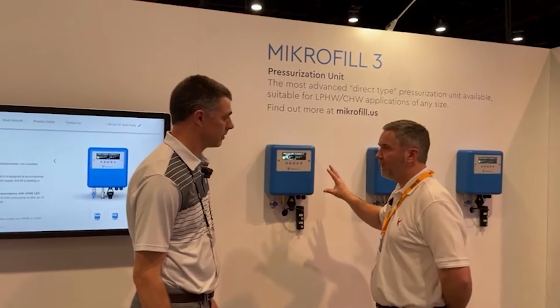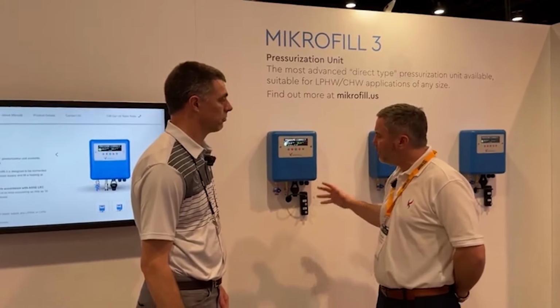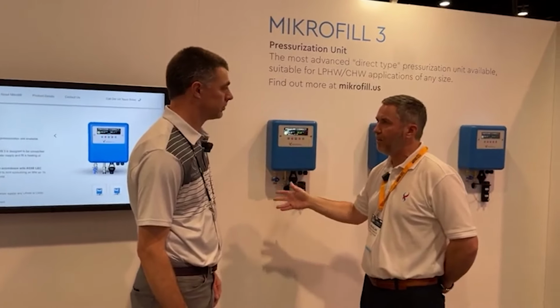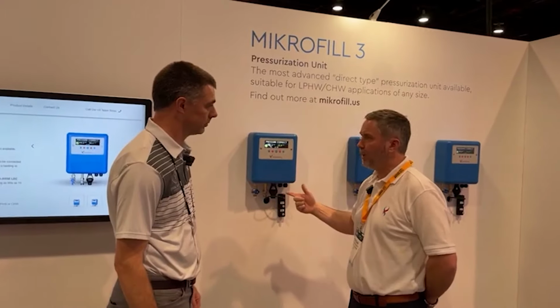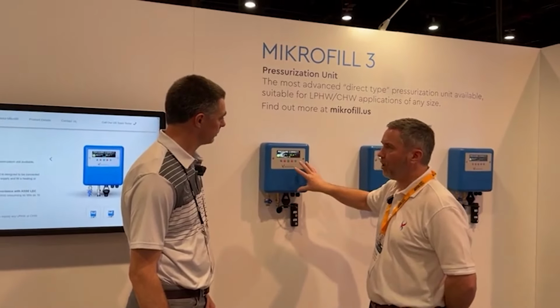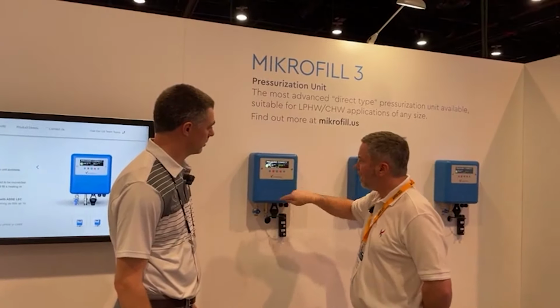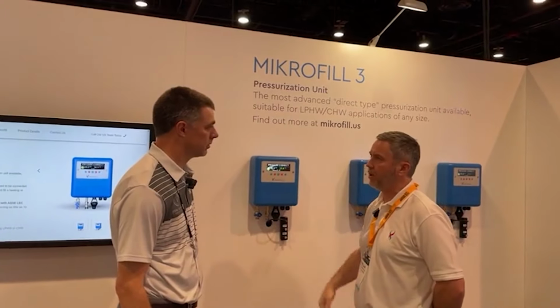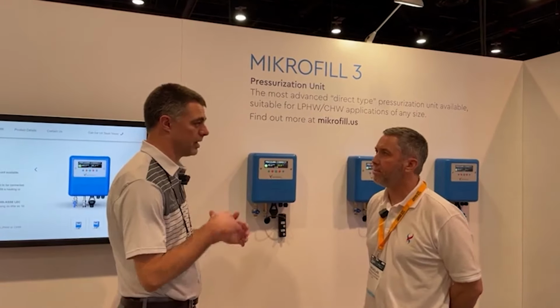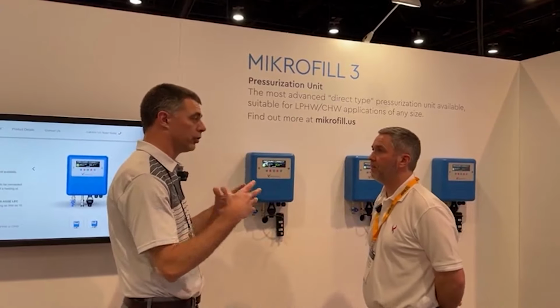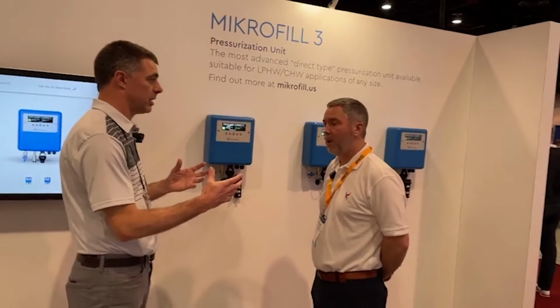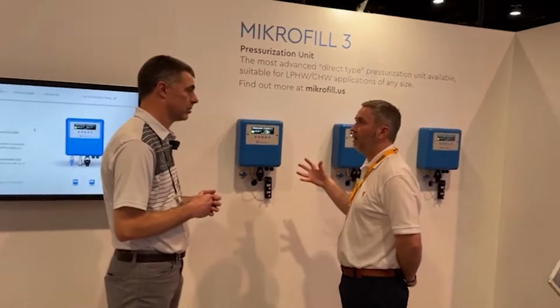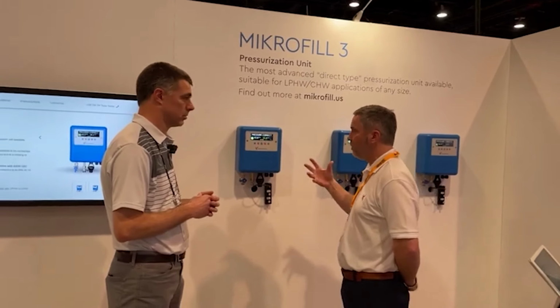So there's no pump, there's no tank, so you have very few moving parts. It's utilising the energy that's already been created by the mains to fill and subsequently top up. And it's one size fits all, and the only thing that changes are the parameters to suit that specific site - so you set the pressure and it just keeps that pressure constant. So does that get rid of an expansion tank then? No, you still require that, because you're now sealing what was maybe previously an open system to a sealed system.